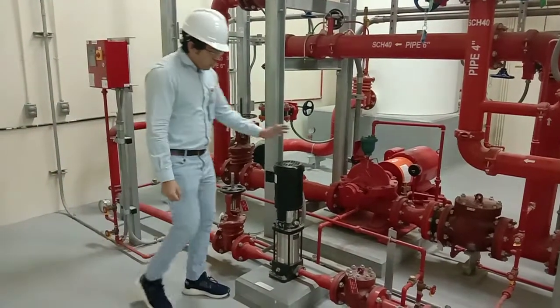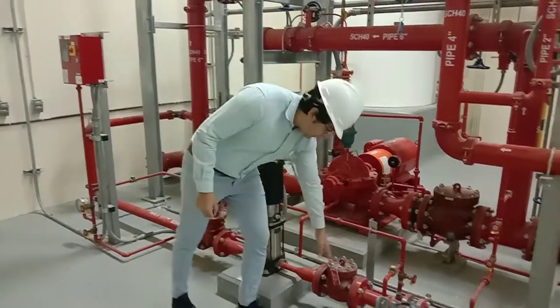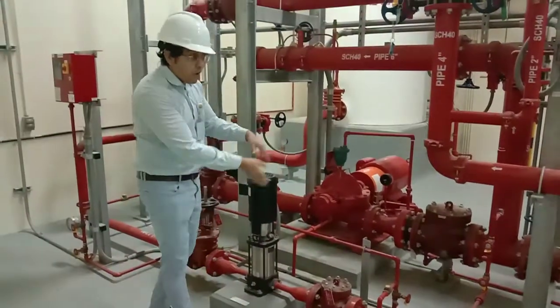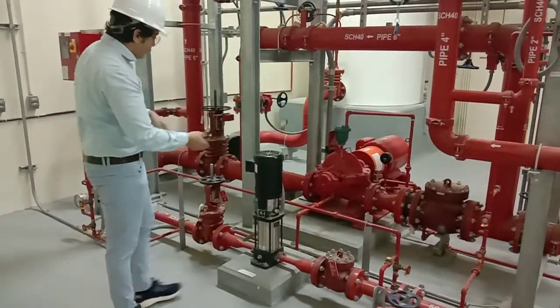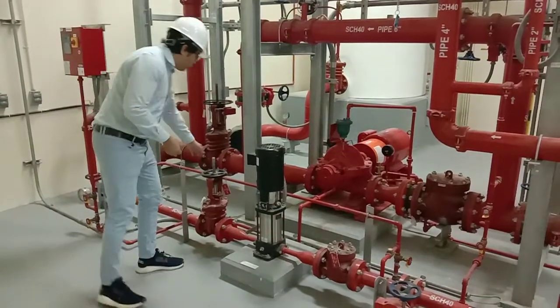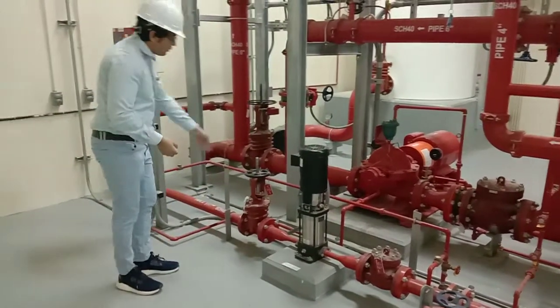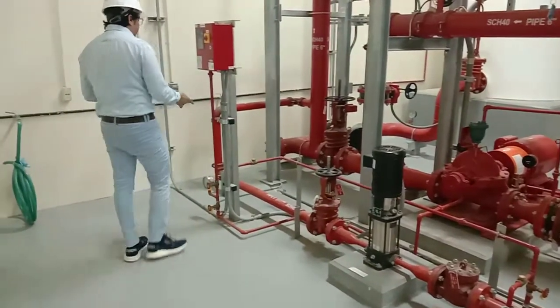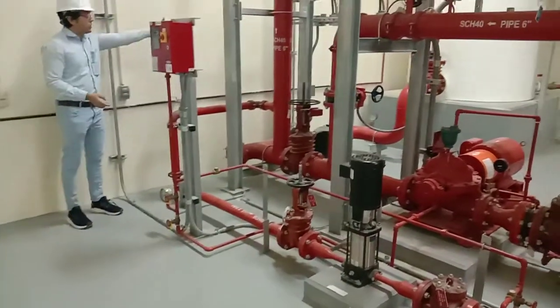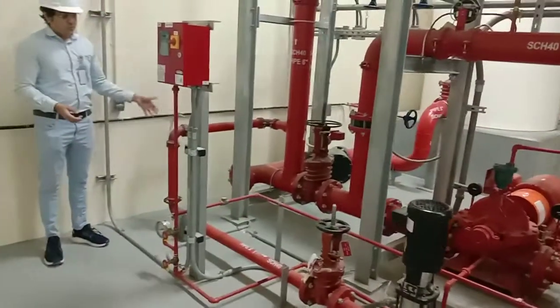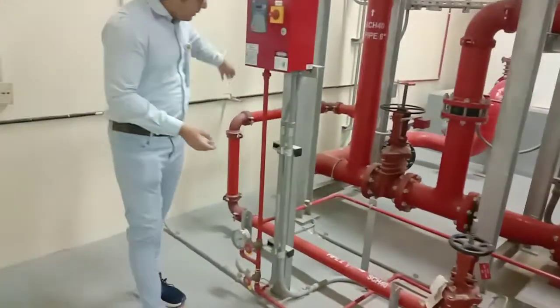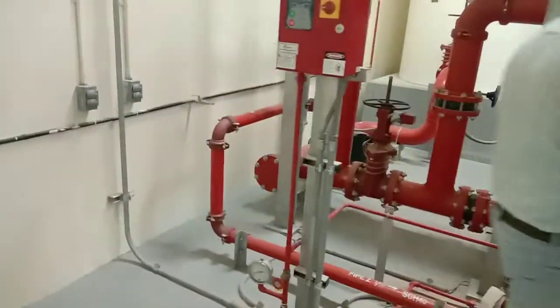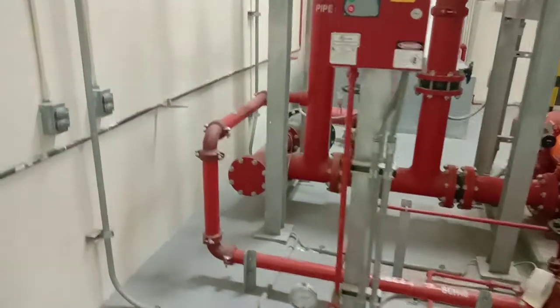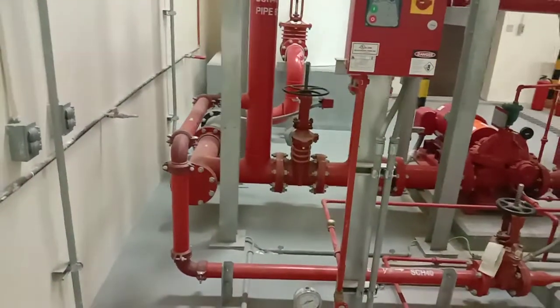Again, in the jockey pump, if you can see, we have a check valve so that the backflow of water can be avoided. In the jockey pump, we have an OS&Y type gate valve in the suction line. Now, the suction of the jockey pump comes from the same suction as the main fire pumps, right? So the water line comes all the way from here, and at this location it gets discharged to the discharge line and does its function.